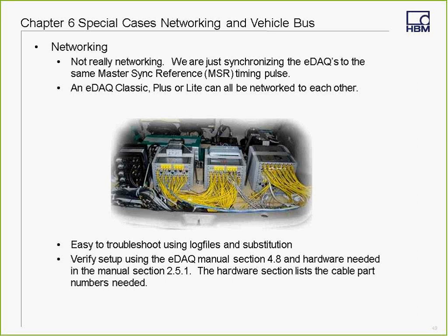The only caveat there would be that they all need to be running the same version of TCE. So if you throw a classic in there, you're going to have to dumb everybody else down to 3.9. Okay, I mean, we're only sharing a common timing pulse, and all the eDAQs have the same capability. So this is easy to troubleshoot using log files and substitution.